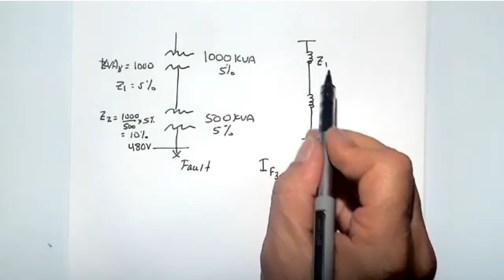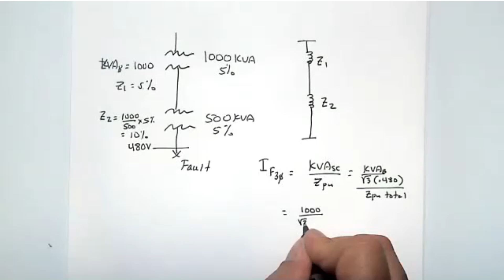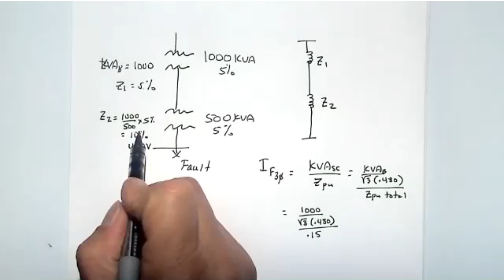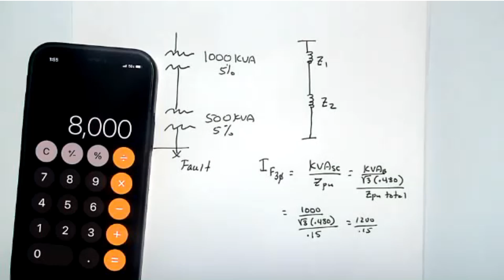So Z1 plus Z2 in that case is 5 plus 10. I would end up with kVA base 1000 divided by the square root of 3 divided by 480, and I think we know what that number is by now, which is 1200, and then we divide it by our total impedance, which is 0.15, or 5% plus 10%. So we take 1200 divided by 0.15, and we end up with about 8,000 amps of fault current.